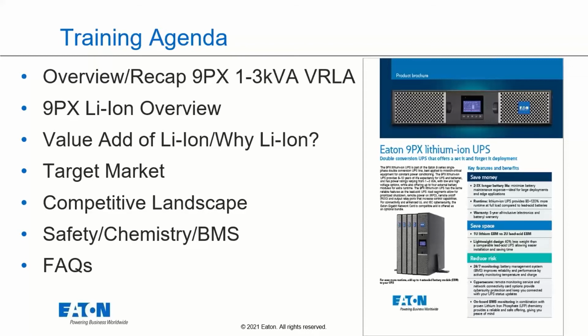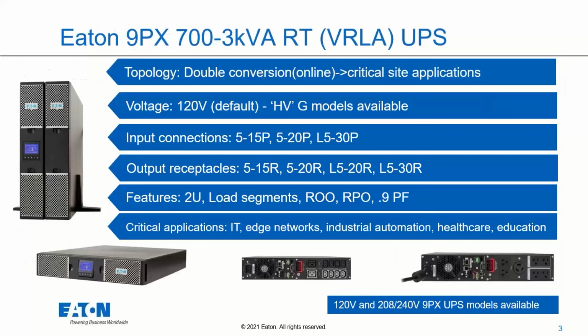So let's jump right into it. First, once again, we're talking about the current portfolio of lead acid to really introduce lithium ion. We're looking at the topology of double conversion online, which provides the highest level of protection by isolating equipment from raw utility power, providing 0 transfer time to battery for sensitive equipment. We see this is all essential for critical site applications, of course. The voltage does include low voltage and high voltage models.